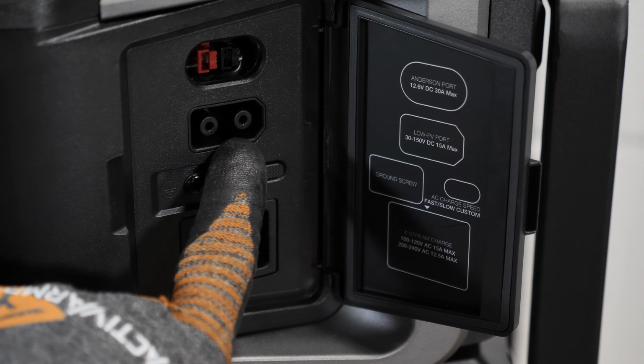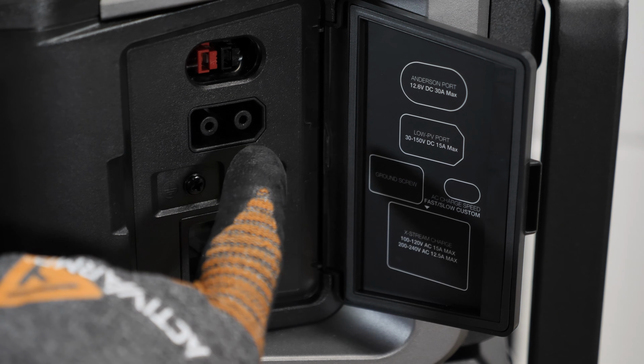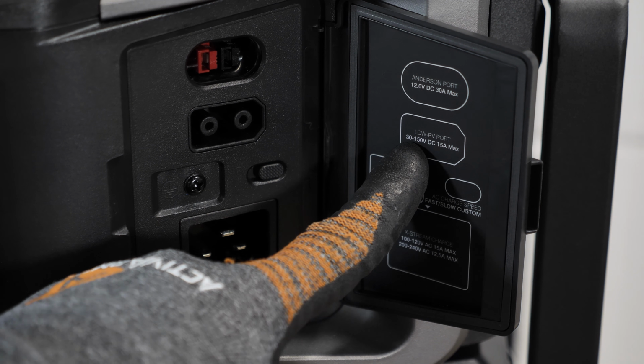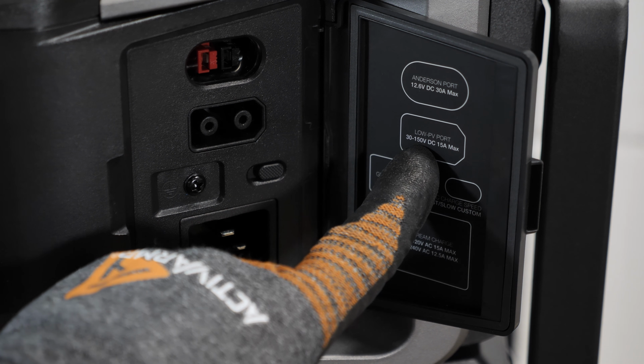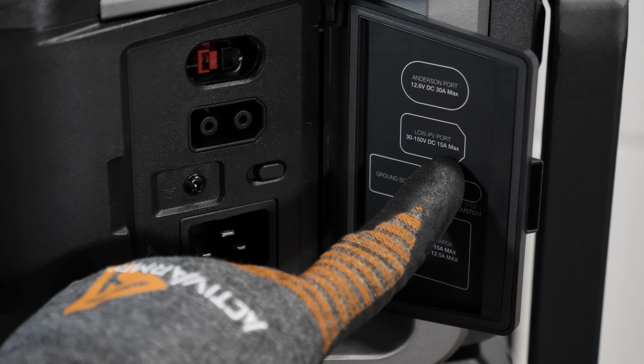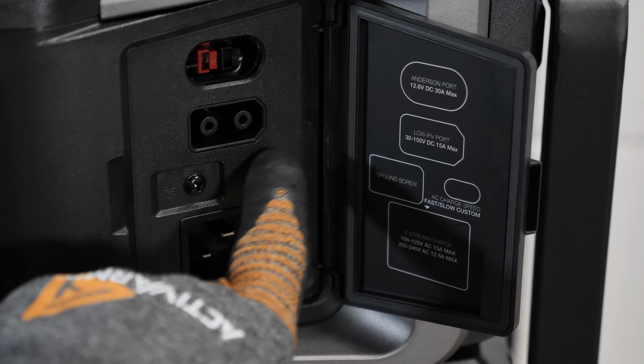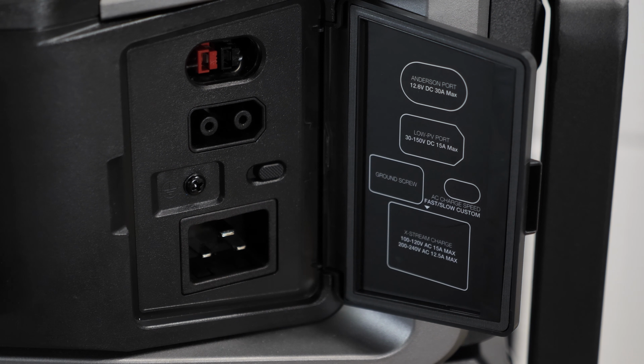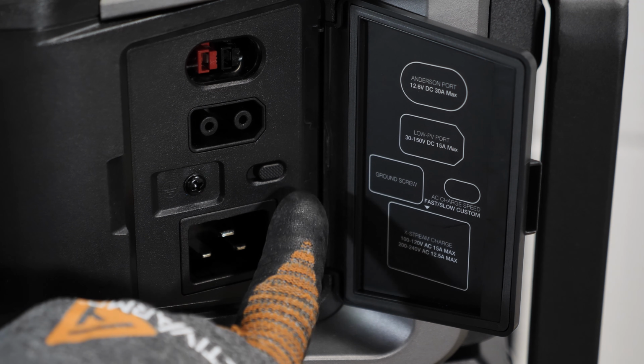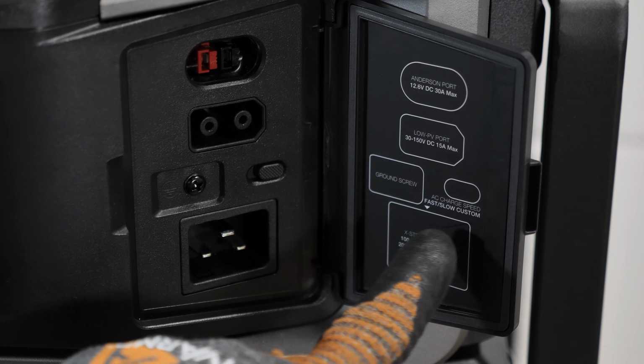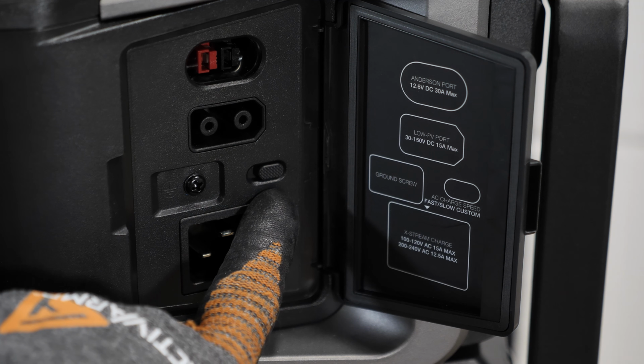Right below that we get your low solar PV port input. Voltage range on that is 30 to 150 volts DC, 15 amp max. That's nice to see for the low voltage PV input. Right over here we have a ground screw, and next to that your slow and fast charge, which again you can adjust inside the app.